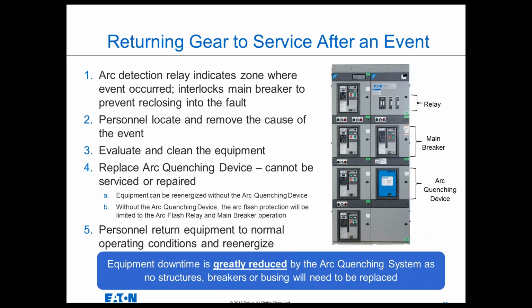But you just have to remember that the protection falls back to the speed of the relay tripping the main. So instead of a 4 millisecond arc quenching time, you fall back to anywhere from a 50 to 60 millisecond clearing time. So your PPE would temporarily be higher until you had a replacement arc quenching device installed. And the arc quenching device can be racked into energized equipment if your safety procedures allow, and then bring the equipment back up to its fully protected state. So moral of the story is, equipment downtime is greatly reduced since repairs will be minimal and most likely completely unnecessary, and the arc quenching device is simply replaced, just like a draw-out breaker would be swapped.